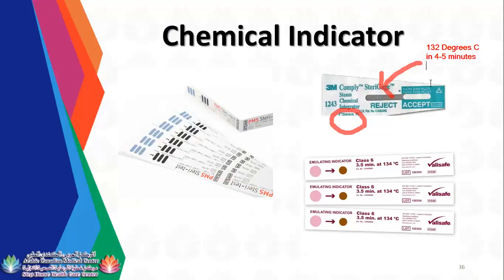Okay, so you need to check your sterilization cycle if it can reach 4 to 5, because there are times, right? It's 3.5 to 5 minutes. So you cannot use the class 5 if your machine will go on 134, commonly 3.5 minutes sterilization process. Okay, please be reminded that the sterilization is 3.5 to 5 minutes.